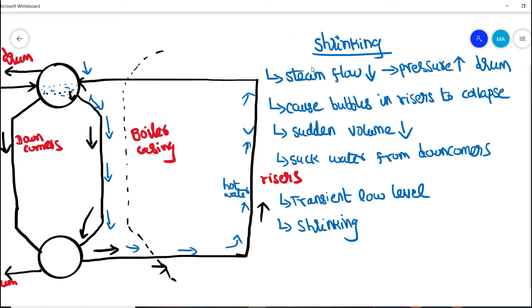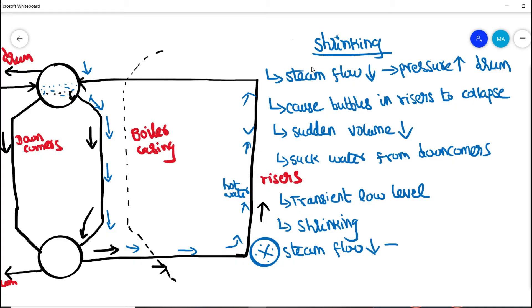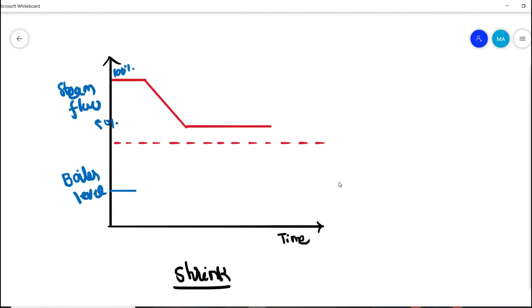What we actually need when steam flow decreases is to reduce or cut the boiler feed water flow. But due to the shrinking effect and the resulting transient low level, the boiler feed water would instead be increased. In the graphical representation — again, x-axis is time and y-axis has boiler level and steam flow — when steam flow is at 100% and suddenly comes down, that causes a shrinking effect in the boiler level.